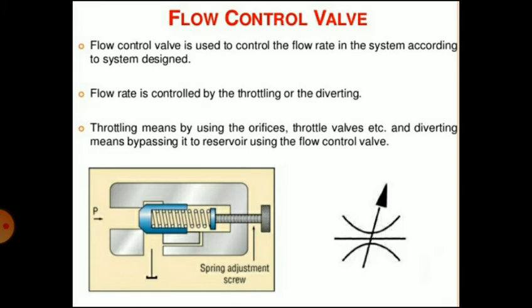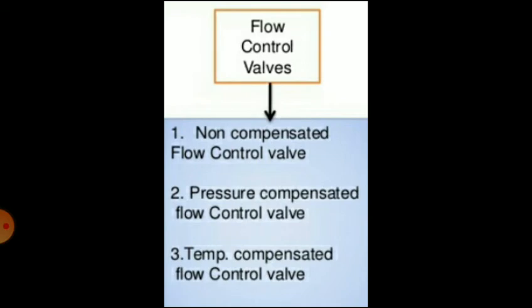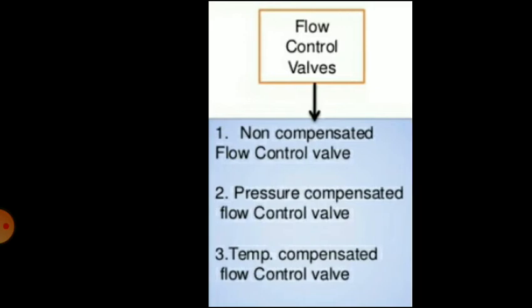Common non-compensated valves are adjustable needle valves, in which flow through them varies with fluid viscosity and pressure. Compensated flow control valves, on the other hand, provide a constant supply irrespective of pressure, viscosity, or temperature changes. Flow control valves can be classified as: first, non-compensated flow control valves; second, pressure compensated flow control valves; and third, temperature compensated flow control valves.